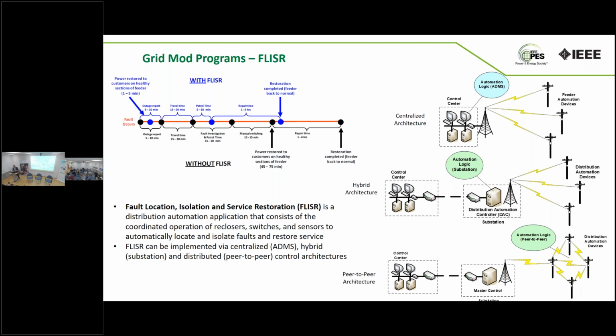That process, if you do it manually, and that's how it used to be done in the old days, can be time consuming: locating the fault, patrolling the line, opening devices, closing devices. What FLISR does is automate that process using advanced relays and reclosers and telecommunications, etc. And instead of spending hours, for instance, in travel time and patrolling, in a matter of minutes sometimes you can restore service and you have isolated the affected area. So the savings can be from hours of interruption duration down to just minutes. So it's quite effective. That's one of those flagship programs.